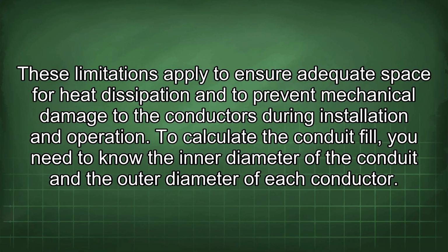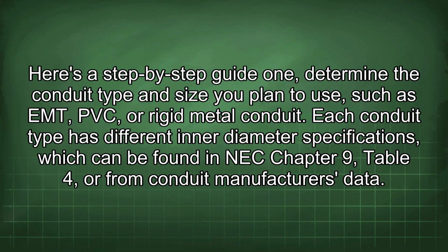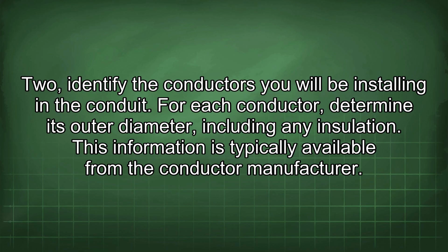To calculate the conduit fill, you need to know the inner diameter of the conduit and the outer diameter of each conductor. Here's a step-by-step guide. 1. Determine the conduit type and size you plan to use, such as EMT, PVC, or rigid metal conduit. Each conduit type has different inner diameter specifications, which can be found in NEC Chapter 9, Table 4, or from conduit manufacturer's data. 2. Identify the conductors you will be installing in the conduit. For each conductor, determine its outer diameter, including any insulation. This information is typically available from the conductor manufacturer.